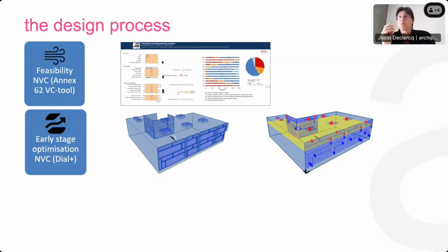As a second step, when you're convinced that it's indeed a feasible concept, we did a single zone dynamic simulation. There are quite some low-level tools available for that, which allow you to check the ventilation rate just by assessing the stack effect, taking no wind effects into account, which brings you mostly at the safe side, and assessing already how it might impact your cooling loads.